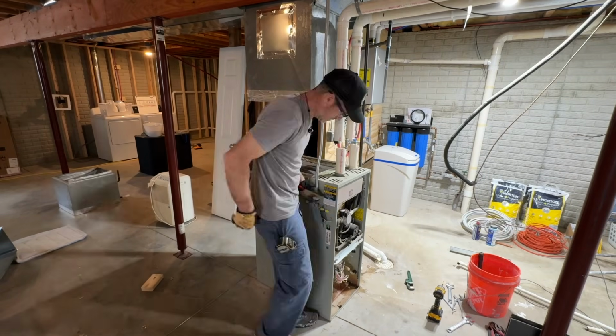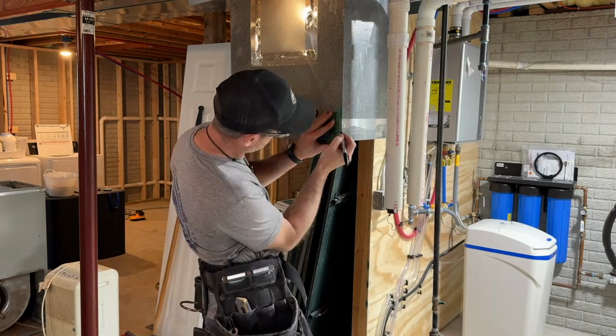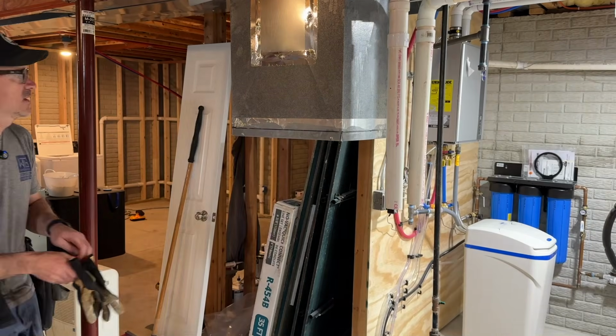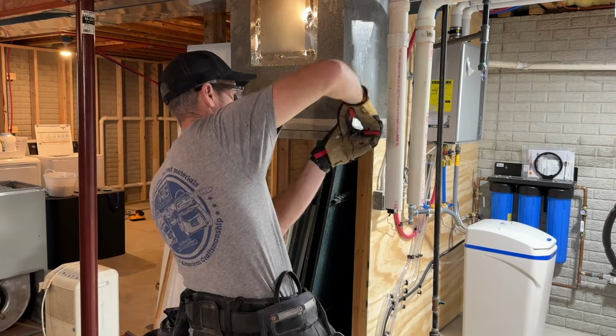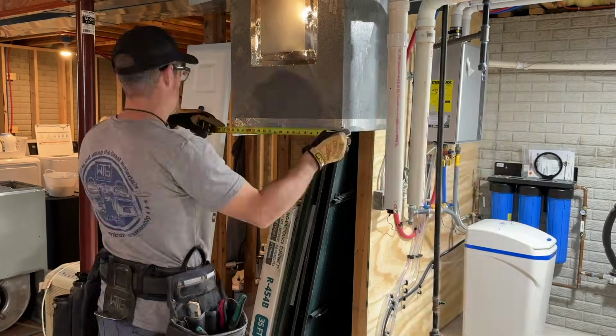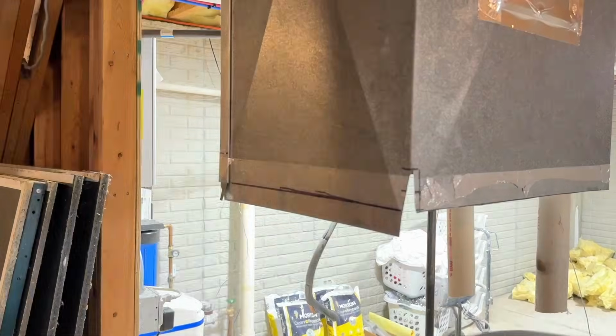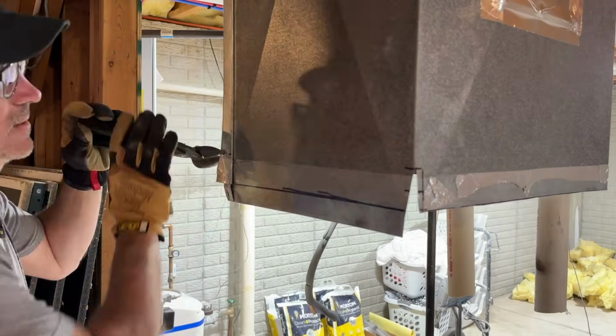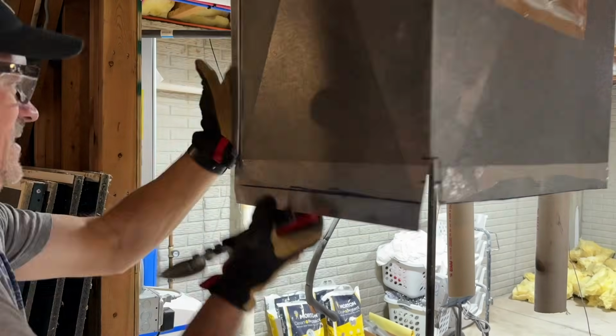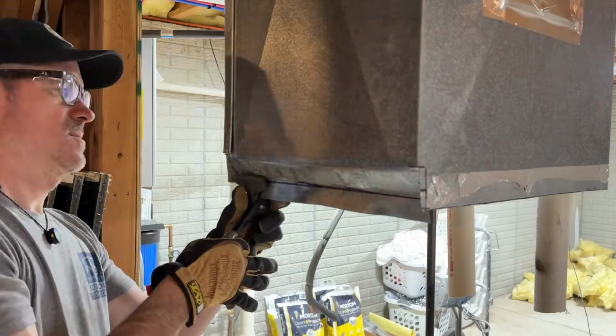What they did is pulled all the refrigerant back into the outside condenser so that it was safe to take the line set off. All right, guys, the system I'm installing is a dual fuel system. It's a heat pump with a gas furnace backup. It should be noted that this is not a DIY product from MRCOOL. It's recommended that it's installed by a certified HVAC technician, or that the project is overseen by an HVAC professional.